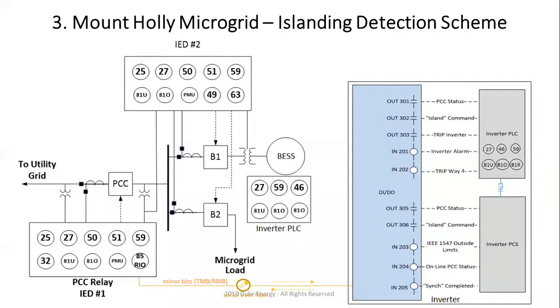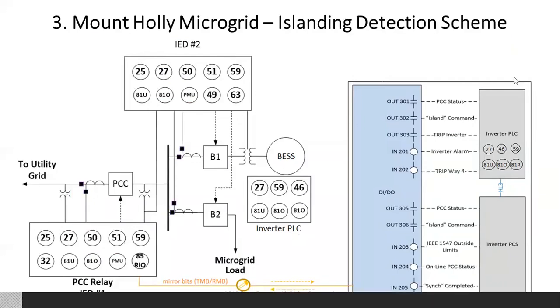There are a couple other things. IEEE 1547 outside limits on the bottom on the PCS. Essentially, that means that the battery can actually detect islanding in some cases before the PCC, so that's why that is done. So essentially, if the PCS does that, what happens is that the PCC relay knows that it needs to open, and a few other things. But essentially, this is how we accomplish seamless islanding. There's a lot behind it over here, but this is just the basic idea. Okay.